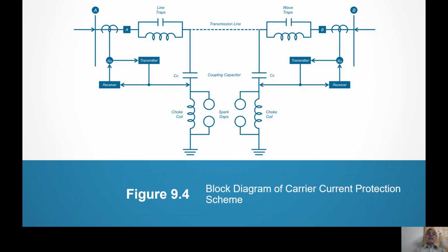At end A there is relay RA, and at end B there is relay RB. When there is a fault between A and B, between two cities, RA will give a signal to breaker A. Breaker A will trip locally. But at the same instant, breaker B should trip. How does it trip? When relay RA operates, it triggers a transmitter also. And that transmitter gives a signal to the coupling capacitor.